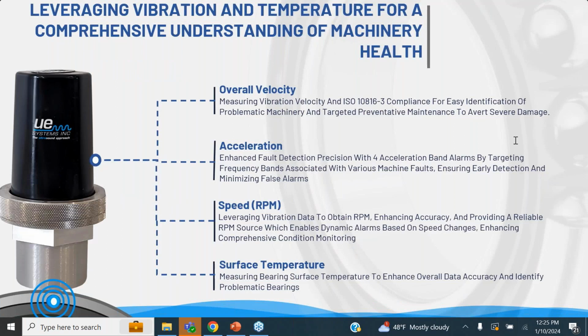And then as we look at these, what we call enhanced insights, as I said, we understand that vibration does add value, especially on a permanent mount sensor. So what we do is a velocity and a full FFT of that acceleration spectrum, which allows us to set up 4 acceleration bands. We will set these alerts up. Now, if you have a background in vibration, you are more than allowed to set up your own parameters. But if you don't, we will work with you to set up those parameters based on that very specific application. With these, we do need more information than we would with your OnTrak wired, especially if it's belt driven. We need sheave size, things like that.